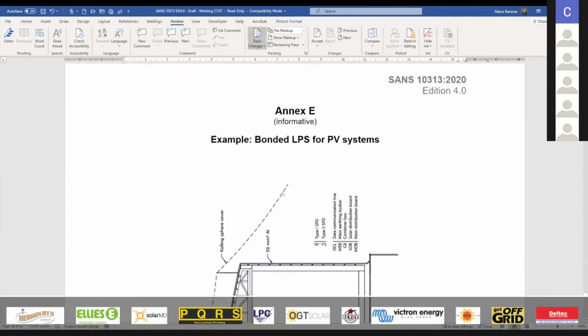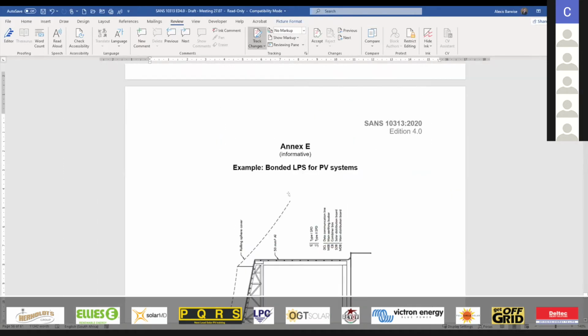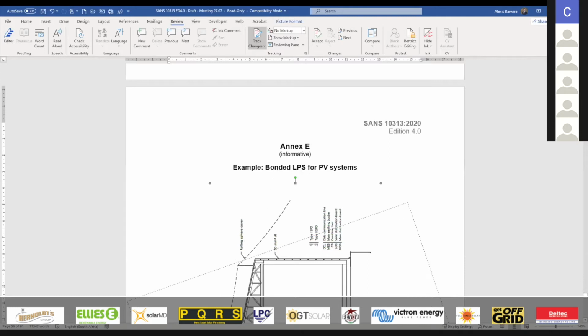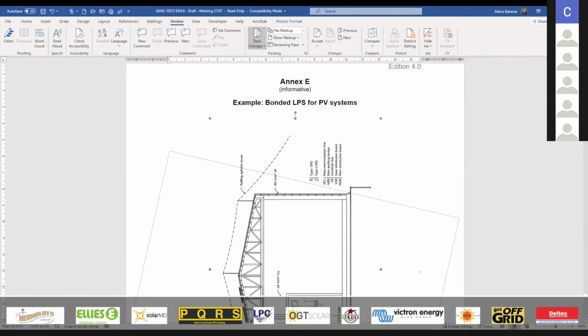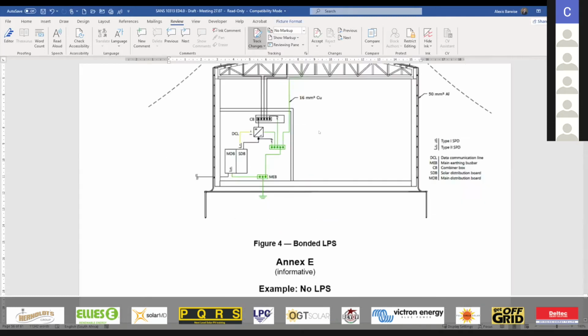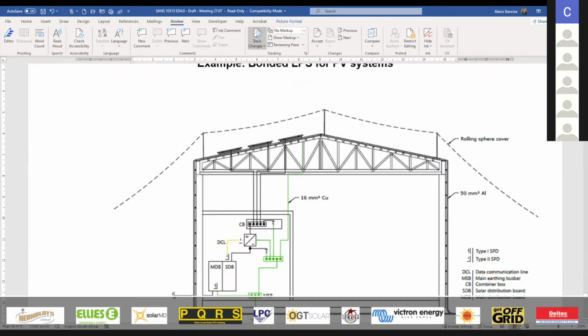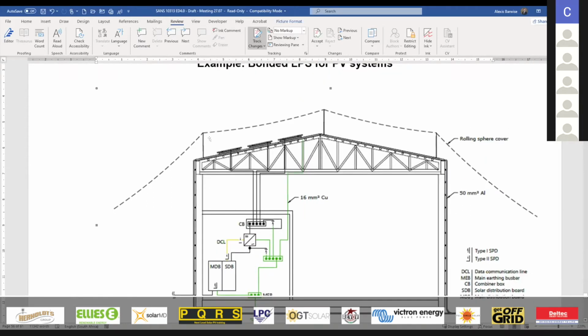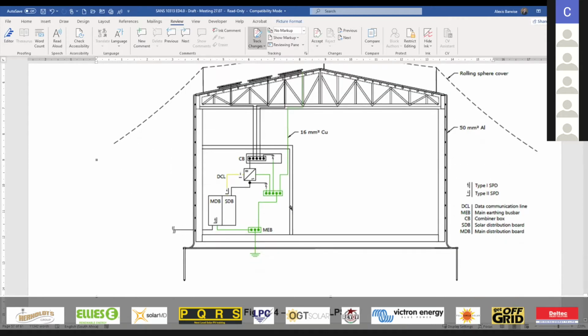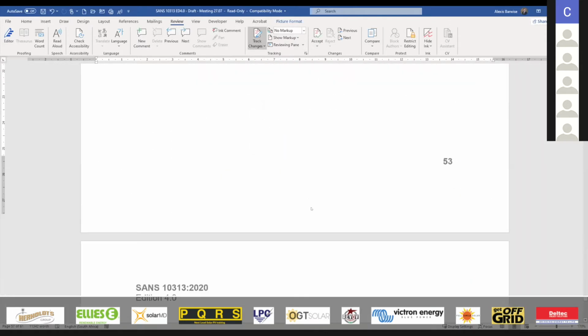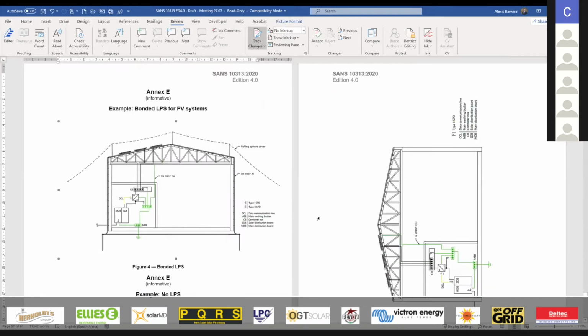In the same breath, if we look at these bonded systems, so something like an IBR sheeted roof, again we would have the masts up, but everything will be interconnected, obviously, because it's one bonded roof. Then we would upgrade the copper conductor to 16 mil squared and the SPDs to type 1, type 2s. You can see also by this bonded LPS drawing, which will also be given to you.